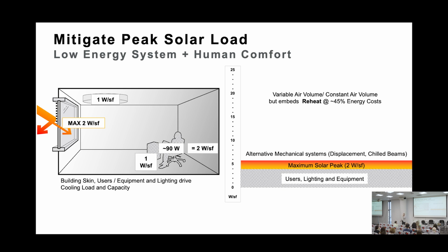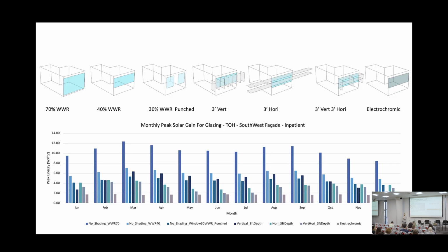If we get 2 watts a square foot and below, we're able to specify an active chilled beam system, or even a radiant slab system, or displacement ventilation. All of these low energy systems are possible if you control that peak solar load, especially in an environment like California.